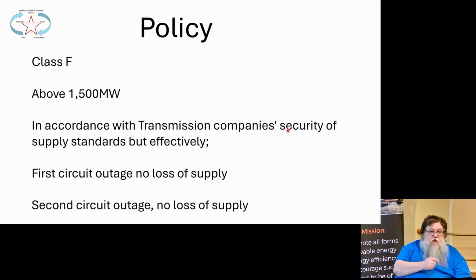And National Grid typically have substations with 4 circuits feeding into each substation. So you can have one out and a fault on another one and you've still got 2 left. National Grid in England and Wales have circuits which run round in rings, and we tend not to have that in the more remote parts of Scotland, though Hydroelectric at the moment are seeking to do that for the Dounreay circuit. They're looking to build another 400 kV line from Caithness down to Beauly, so that circuit that goes up through Beauly, from Beauly up to Dounreay and back down to Beauly again, will have 4 circuits. They'll be the same as it is in England and Wales and the Central Belt of Scotland, actually.